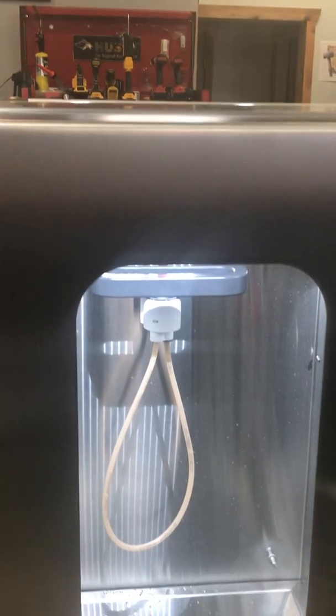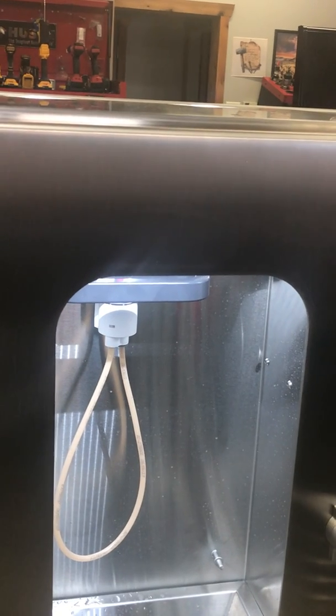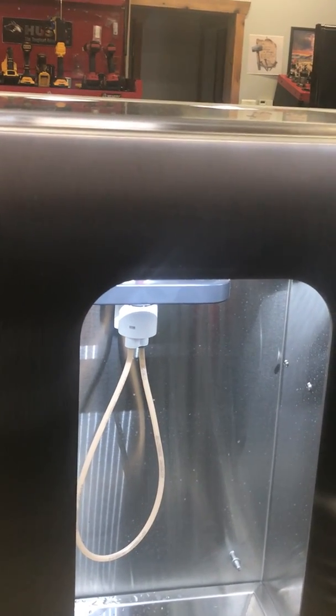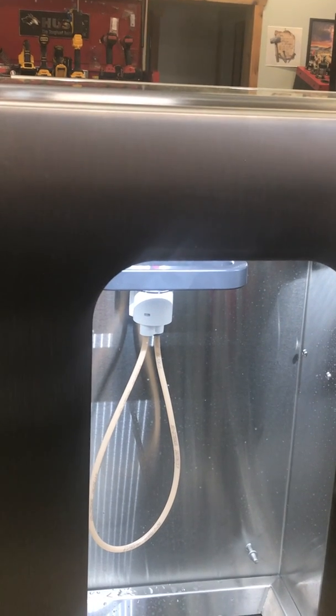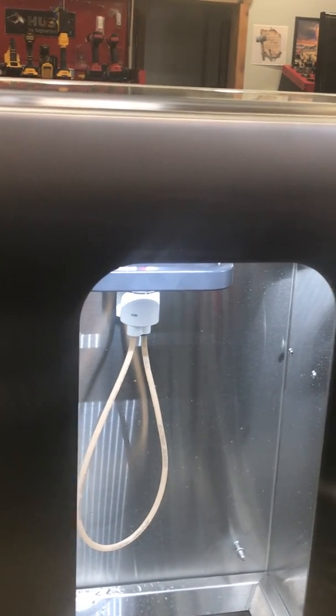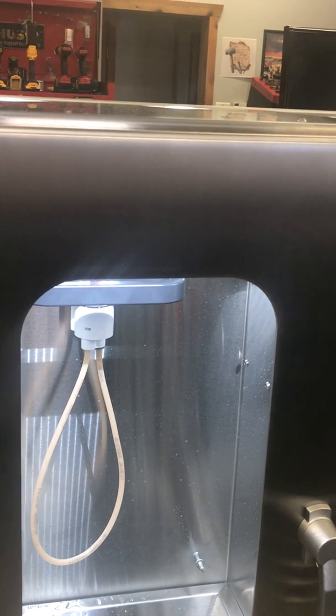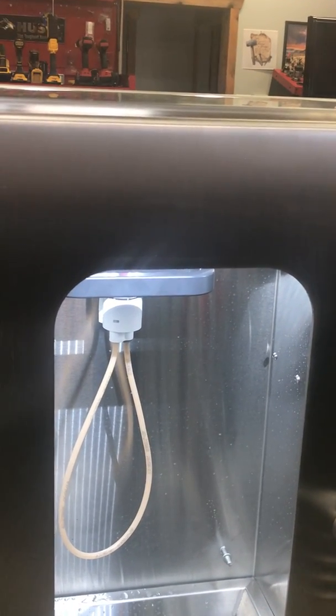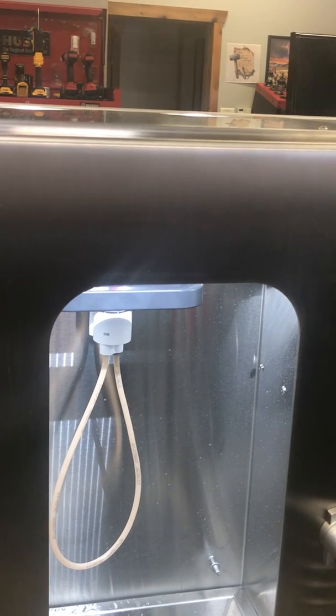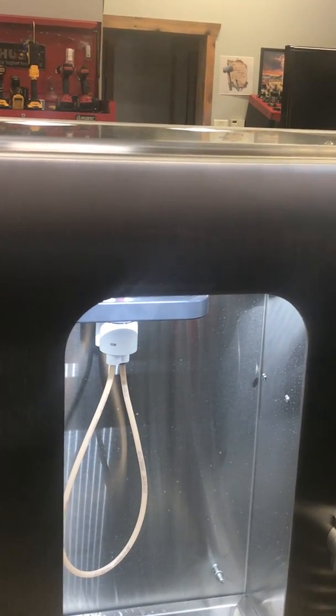It's 374. Hold on, look. I looked at it and then came back down one. That was fun trying to hold it perfect. Now it should go up to 1,000. It's flushing right now. And if you decide you don't want to flush for the second test, you just go back in the parameters of burst and say flush at 0. Yeah, it's all gone. Just like that. Hit 1,000.